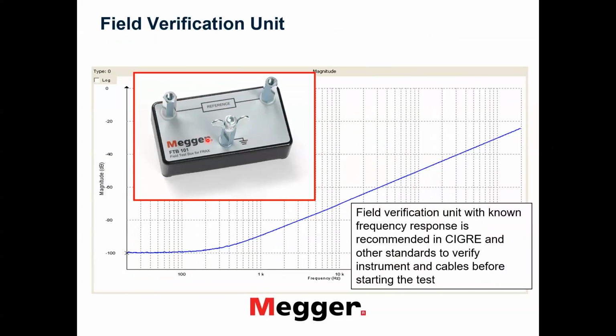Also, I mentioned the field verification unit, and this is something which is also put into standards, recommended by the standards to have such a box in order to verify your test hardware integrity, so to speak. So you make a measurement on this box and you expect to have a curve like this. If you don't have a curve like this, then there is something wrong. Most probably it is cable contacts which are loose, or you have forgotten to connect something, or there is a short circuit between measurement clamp and ground and such things. But the field verification box is essential, and it is actually quite good to make sure that your hardware is working and fine.